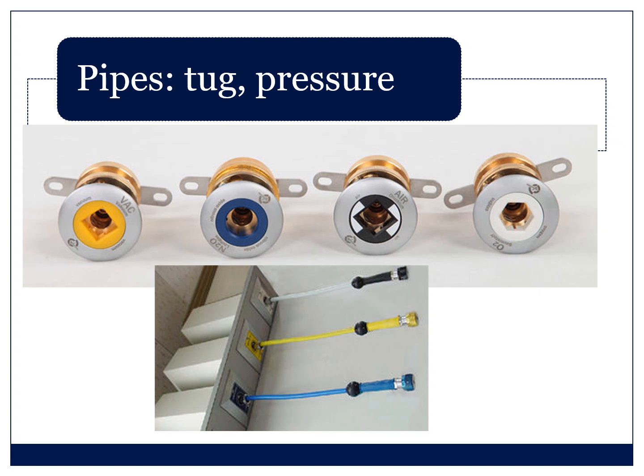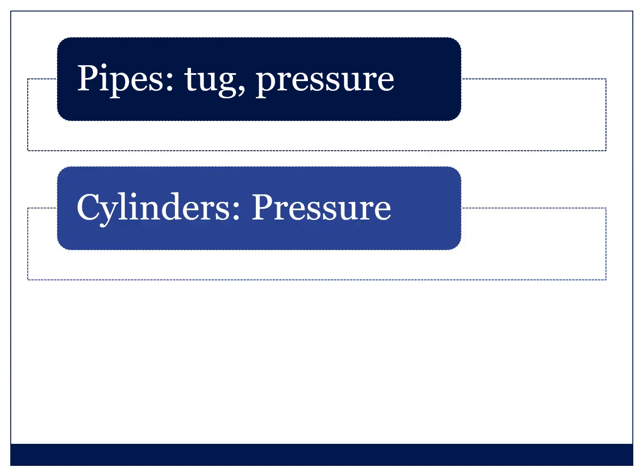The next thing to check is the piped air supply. So there's a central supply that delivers to terminal outlets. These are specific to each gas. They're individually shaped, labeled, and color-coded, and there's a thing called a diameter index safety system. So basically, you need to go to the wall and check that the correct colored pipe is in the correct outlet. They don't fit in the wrong outlets, so they should all be in the right ones, but sometimes they're not seated properly, so you give them a little tug, make sure that they're nicely and firmly attached, and the pipeline pressure is sufficient. They should be about 4 bar.